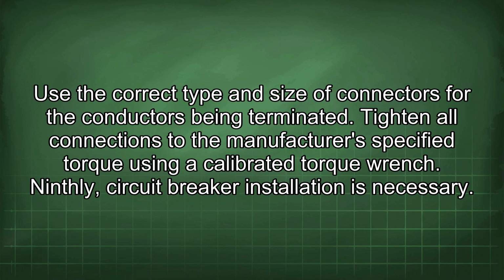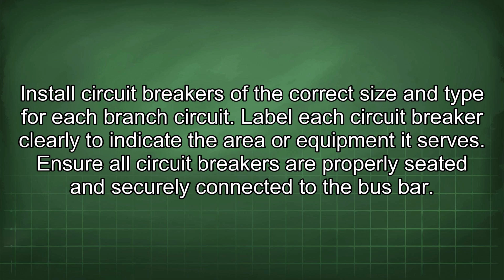Ninthly, circuit breaker installation is necessary. Install circuit breakers of the correct size and type for each branch circuit. Label each circuit breaker clearly to indicate the area or equipment it serves. Ensure all circuit breakers are properly seated and securely connected to the bus bar.